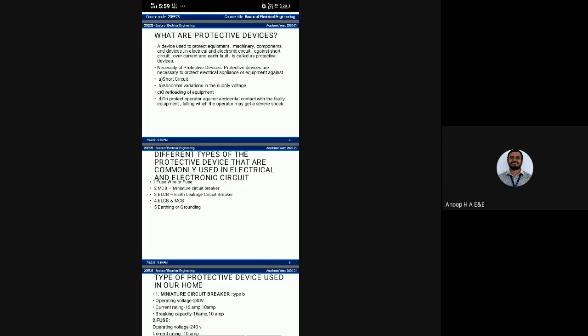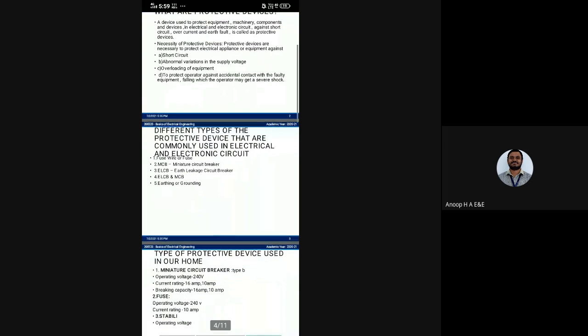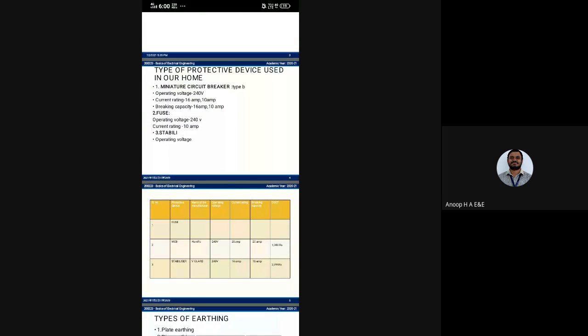Protective devices are necessary to protect electrical appliances or equipment against short circuit, abnormal variation in the supply voltage, overloading of equipment, and to protect the operator against accidental contact with faulty equipment, following which the operator may get a severe shock. Different types of protective devices commonly used in electrical and electronic circuits are fuse wire or fuse, MCB which stands for miniature circuit breaker, and ELCB which stands for earth leakage circuit breaker, and earthing or grounding.